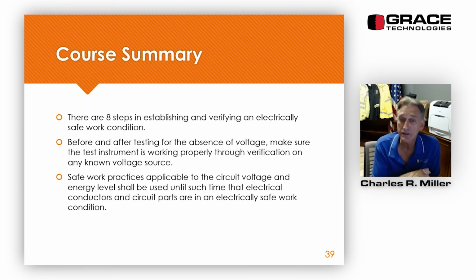We covered that there are 8 steps in establishing and verifying an electrically safe work condition. Now, step number 8 is typically for over 1,000 volts: the temporary electrical safety grounds. Before and after testing for the absence of voltage, we have to make sure that the test instrument is working properly through verification on any known voltage source. If you can remember live, dead, live, that absolutely helps. Safe work practices that are applicable to the circuit voltage and energy level have to be used until the electrical conductors and circuit parts are in what's defined as an electrically safe work condition.